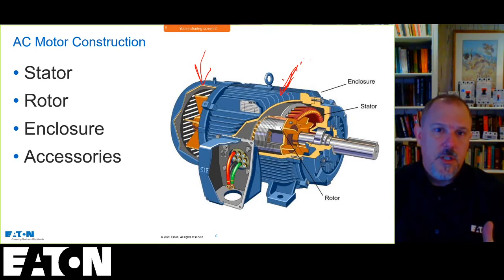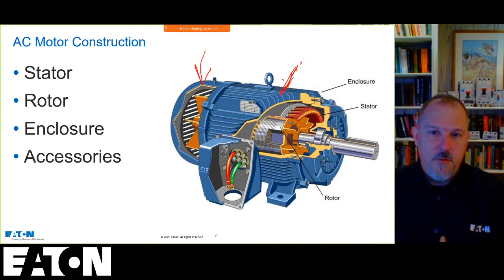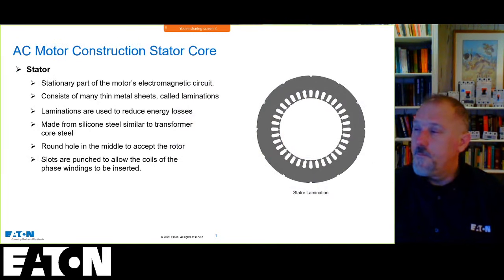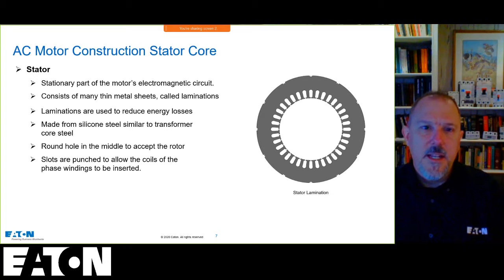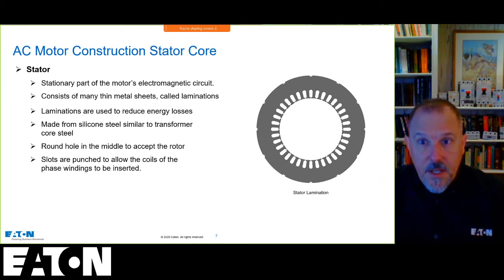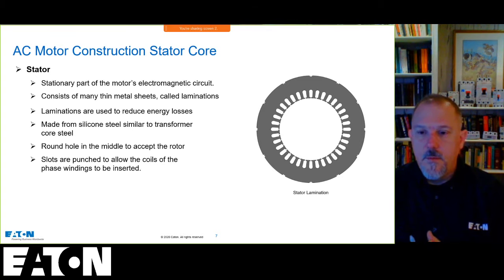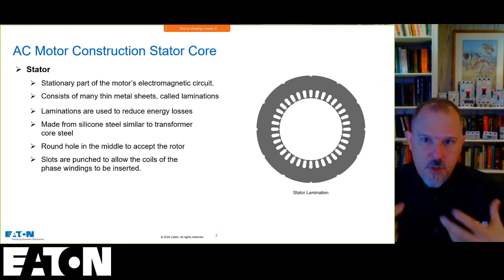When you see motors that are constructed in this way, with all the fins and that built-in fan taking advantage of the rotor that's turning, it is all there to help decrease the impact of heat on that equipment or device. So the stator is the stationary part of the motor that we wire things to. We will put 480 volts or whatnot on the stator, and based upon how many phases we have in there, it helps generate the rotating fields that will help turn the shaft.